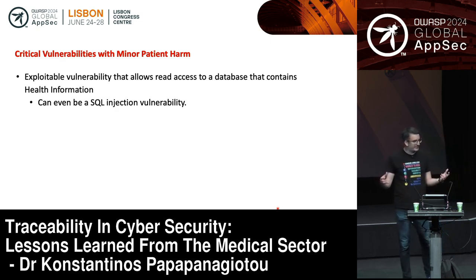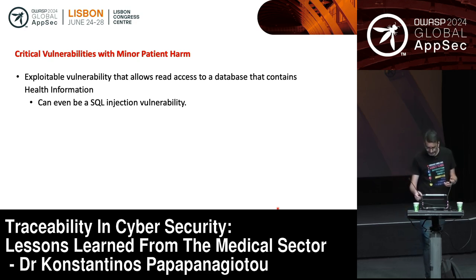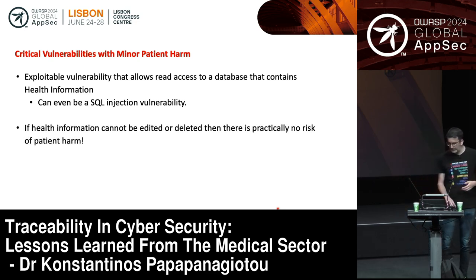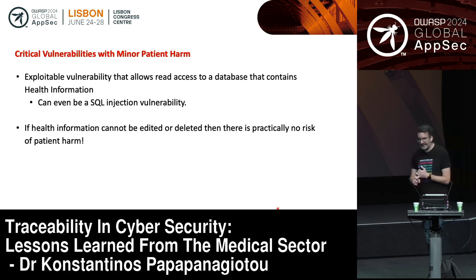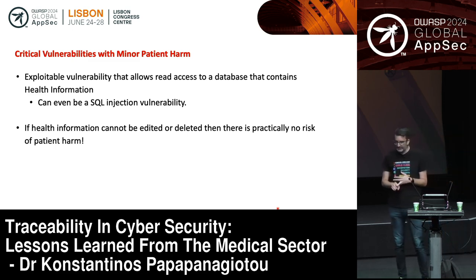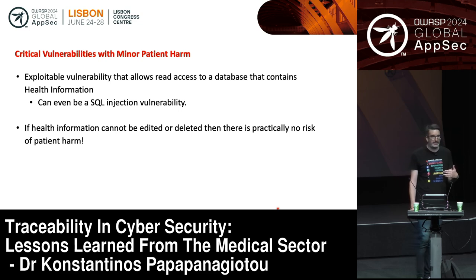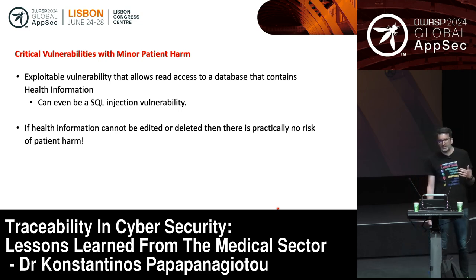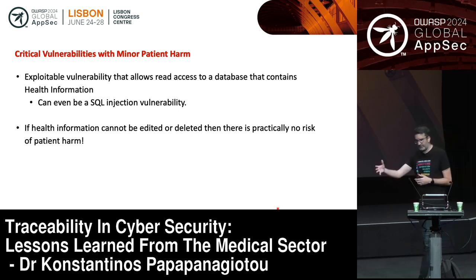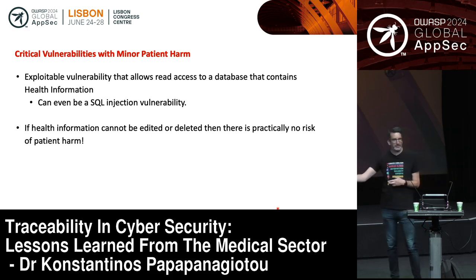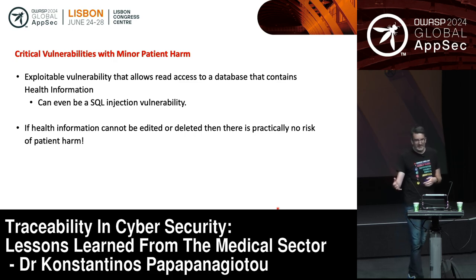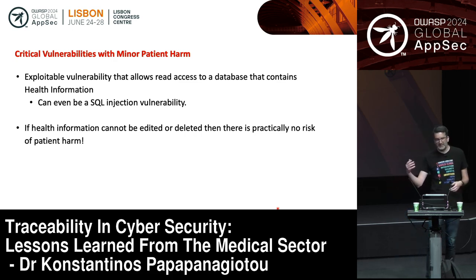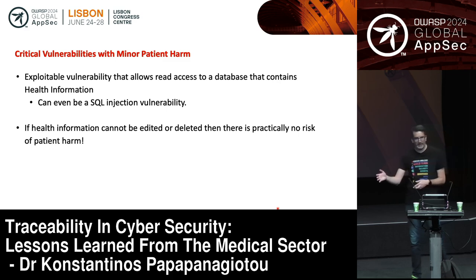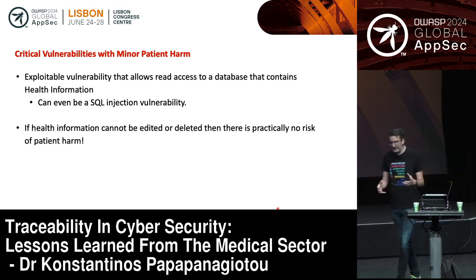Is this important from a medical device perspective? It depends. If health information cannot be edited or deleted, this vulnerability might actually lead to no patient harm risk. You may read healthcare information, but you cannot harm the patient since you cannot change it. And if that's the case, the FDA doesn't care. It's not a significant vulnerability. You don't need to do anything about it. I'm exaggerating a bit here, but it's not far from reality.